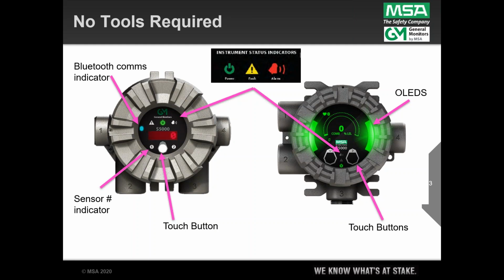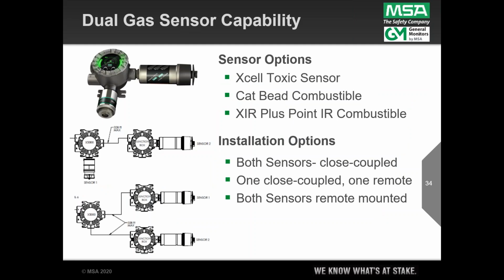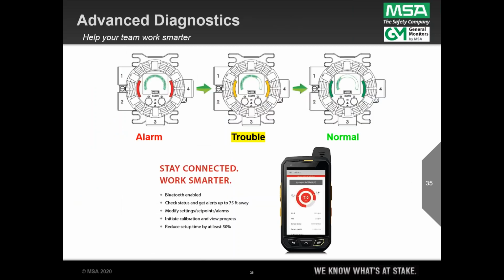And also, I think Adriana told me the temperature rating on the S5000 is a little better. So it's a little higher temperature, or maybe lower. I think it's just a little better temperature rating on it. I'll have to validate that, but I remember her telling me that. They both support dual gas capability, right? So we can have a toxic, a cat bead, a point IR, and then you can set them up different ways, right? This is on the lower left. You can have both sensors close coupled, or you can have one sensor on the transmitter and one remote, or you can have both sensors remote and run it back into the transmitter. So I just wanted to show those options out there.